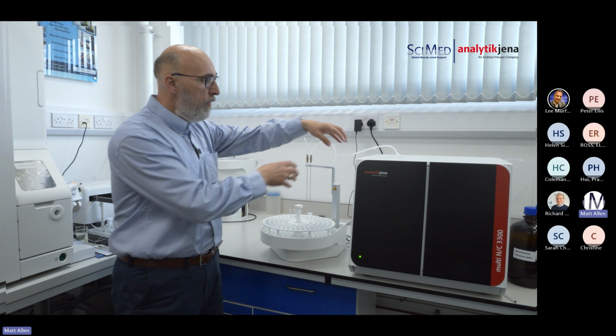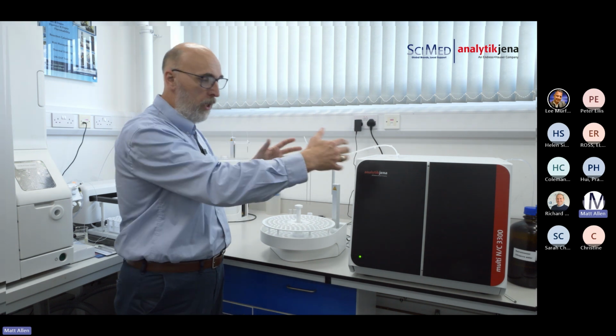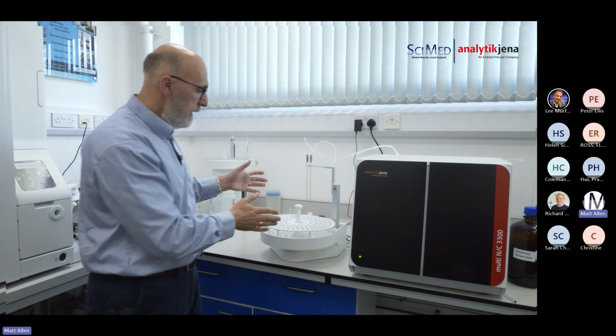So on the 33, and the same with the 43, we have a choice of 3 different auto samplers. We have a small capacity 10 position auto sampler that takes 10 vials, 50 ml vials. There's a 21 position auto sampler, 21 50 ml vials. They both hang off the side here, so it decreases the footprint. And each of those has a dilution option, so effectively you can double the sample quantity with automated dilution options.